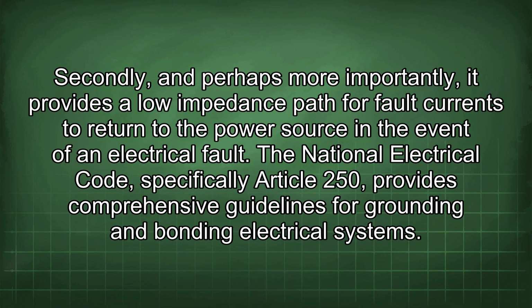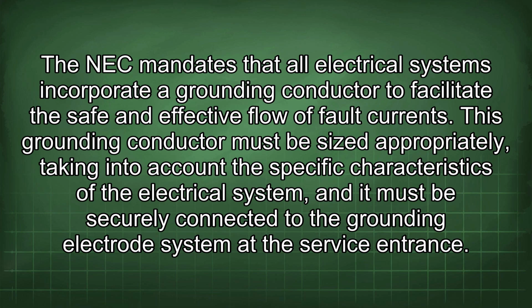The National Electrical Code, specifically Article 250, provides comprehensive guidelines for grounding and bonding electrical systems. The NEC mandates that all electrical systems incorporate a grounding conductor to facilitate the safe and effective flow of fault currents. This grounding conductor must be sized appropriately, taking into account the specific characteristics of the electrical system, and it must be securely connected to the grounding electrode system at the service entrance.